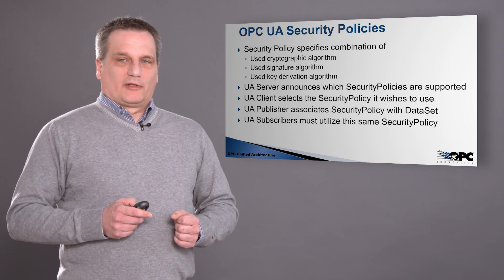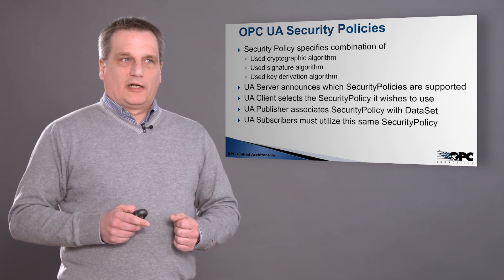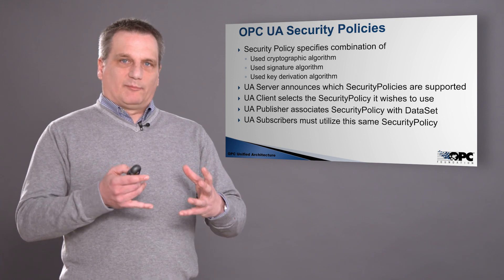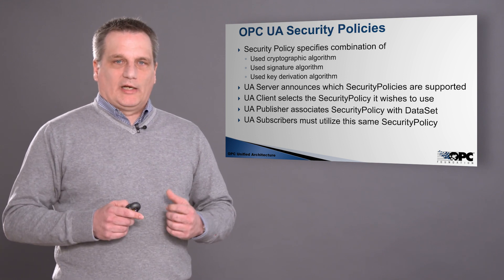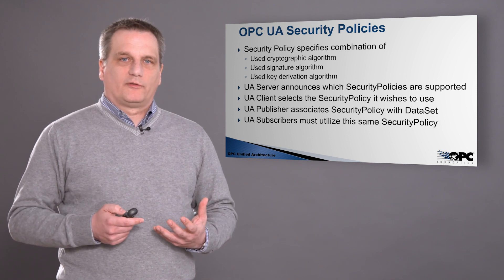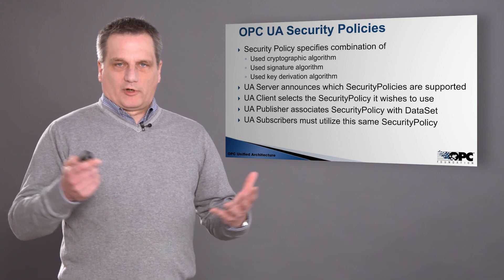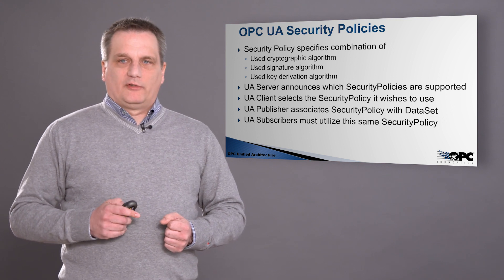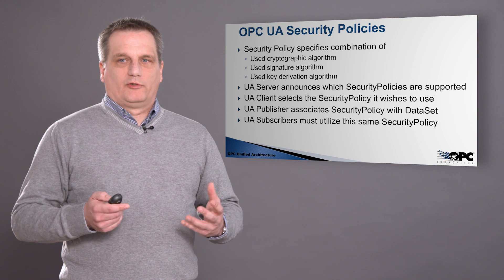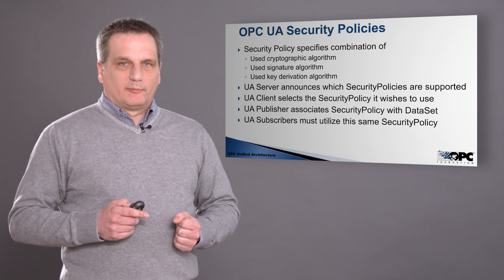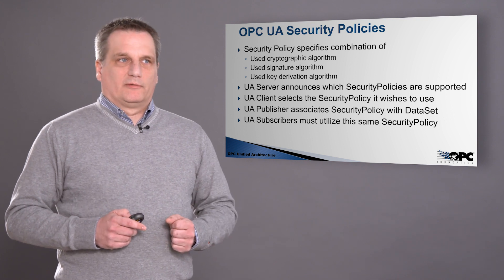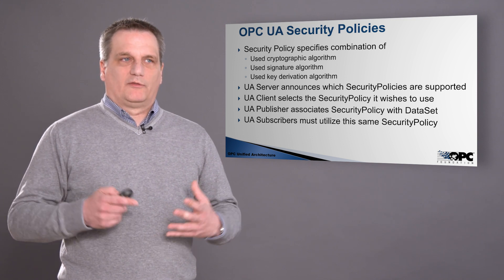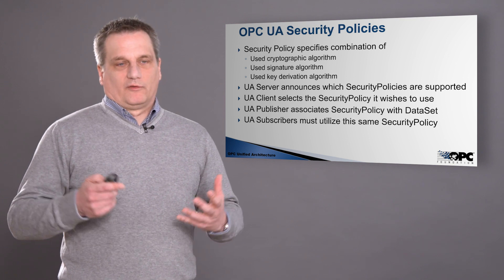Security policies are used to describe the cryptographic algorithm, the signature algorithm, and the key derivation algorithm — all described in one security policy. An OPC UA server announces the security policies it supports for the different endpoints it offers to connect to. The client can read out these policies and then decide which one to use — typically the highest available — to connect and encrypt the information. For publishers, the security policy is associated with the data set and the security group.